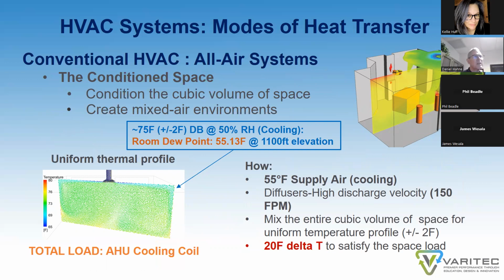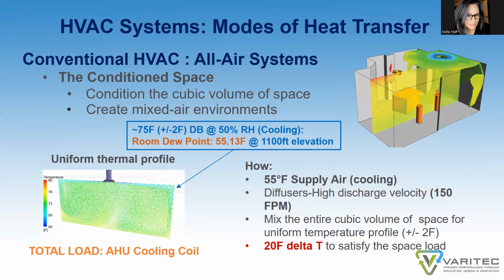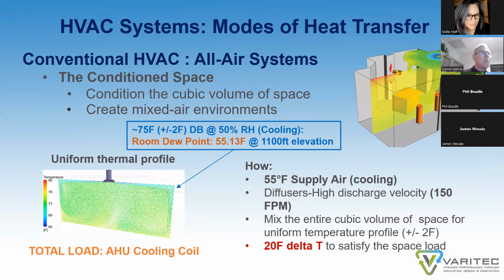And we roughly see that at about 75 degrees dry bulb, 50% RH. 50% RH is certainly a condition we can achieve here in Phoenix, Arizona during our monsoon months. And we condition that space by providing 55-degree supply air optimally. The fact of the matter is, many of our packaged DX units don't even achieve 55 degrees, and we want to achieve 55 degrees to wring moisture out of the air, the mixed air condition the coil sees, so we can hopefully control building humidity levels.